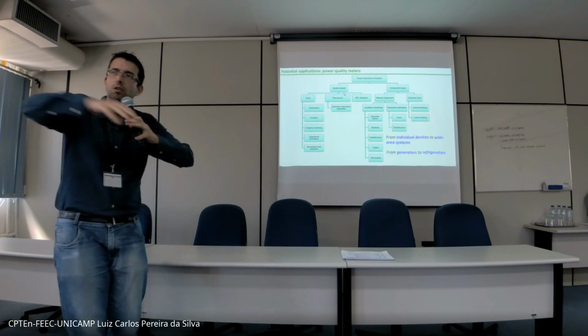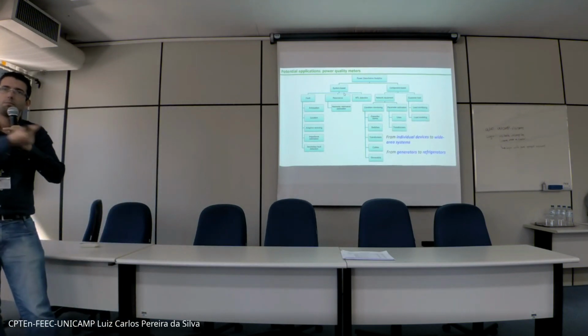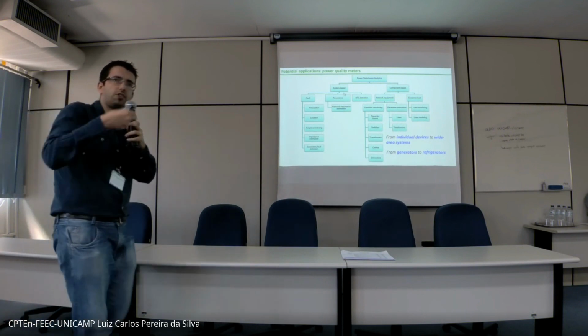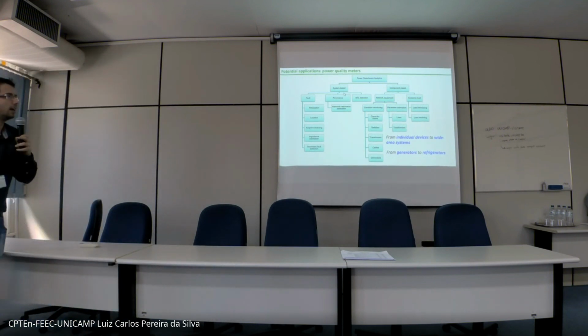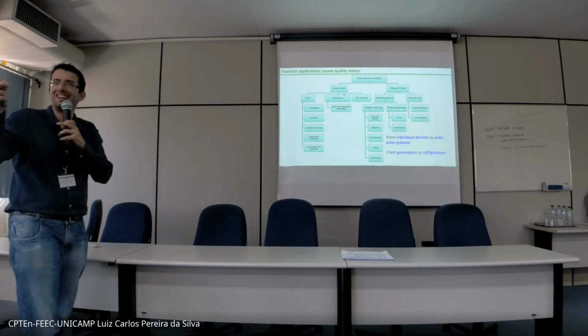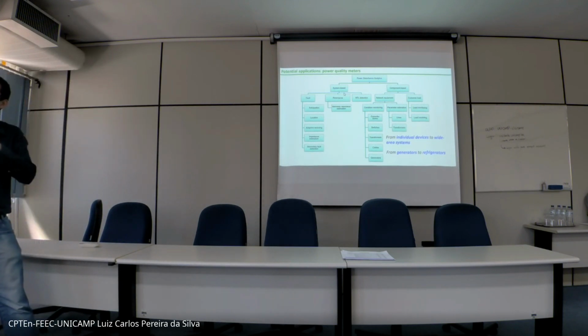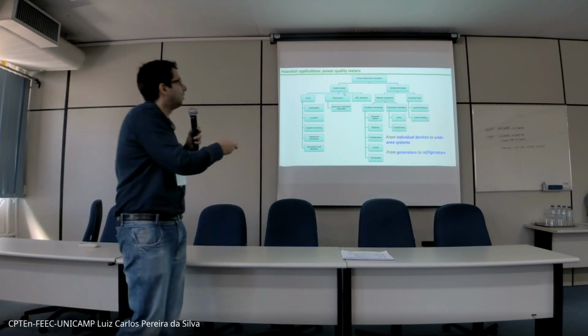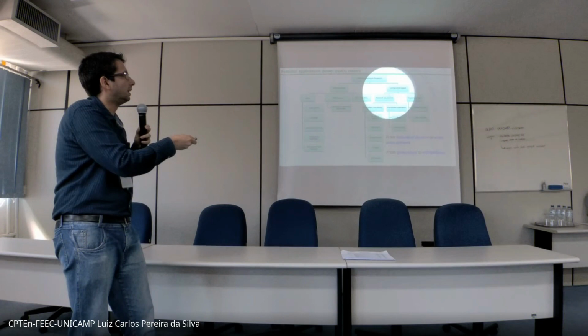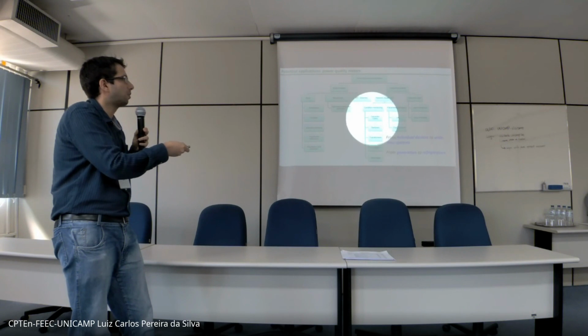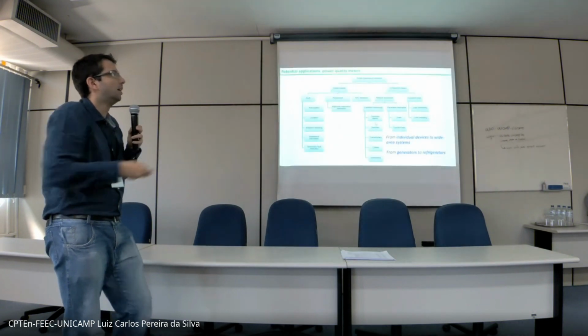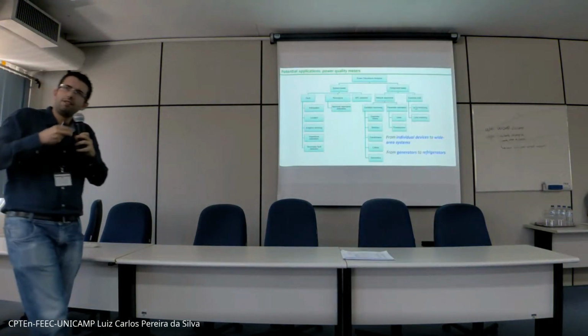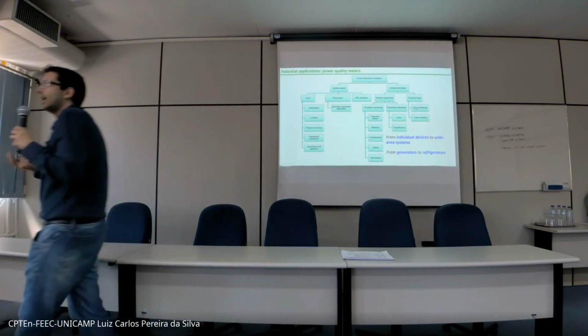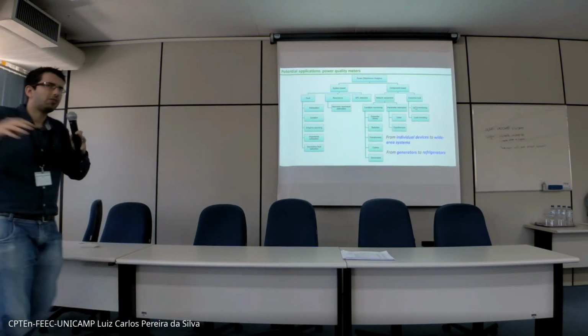Here I'm talking about the whole system - resonance analysis, for instance. If you have power quality meters installed in the grid and process the data properly, you can identify these issues. The challenge is the data analytics: how to process and understand the data. You also have component-based monitoring, detecting the operating conditions of capacitor banks, switches, transformers, lines, as well as load monitoring and modeling.